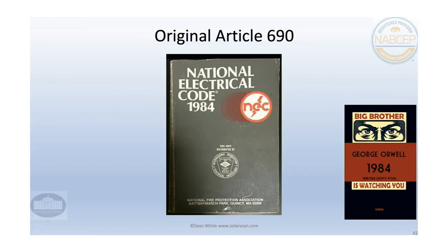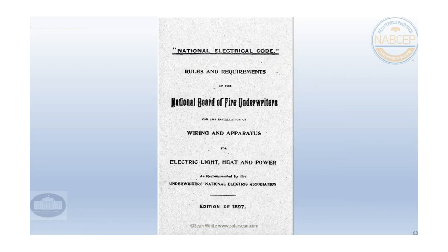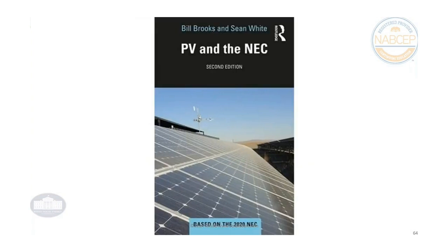Okay, so now we're getting more into the code. 1984, NEC was the first one that had Article 690. And the earlier versions, up until they came up with Article 706, included actually more batteries in 690 than it did in 480. And then they took the battery part out of 690 and they made it its own separate Article 706. There's the 1897 National Electrical Code, which is kind of neat. Some battery stuff in there.